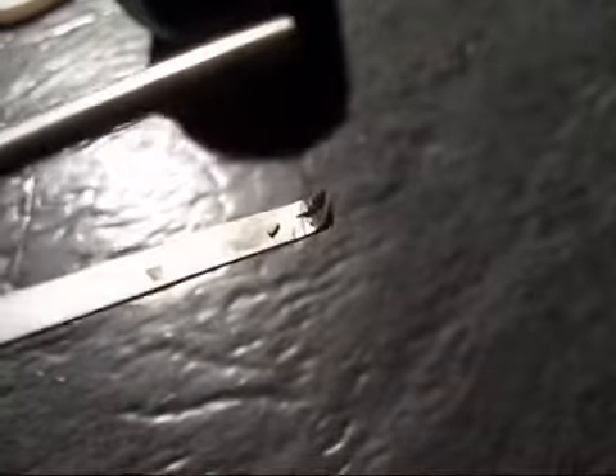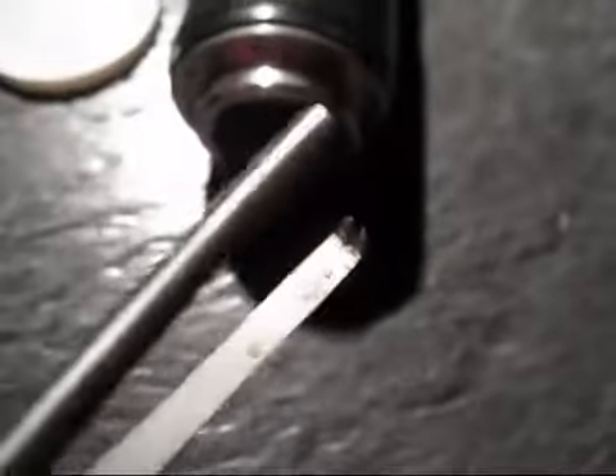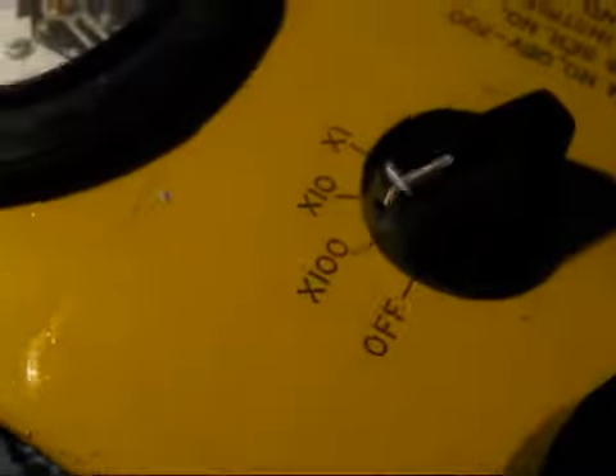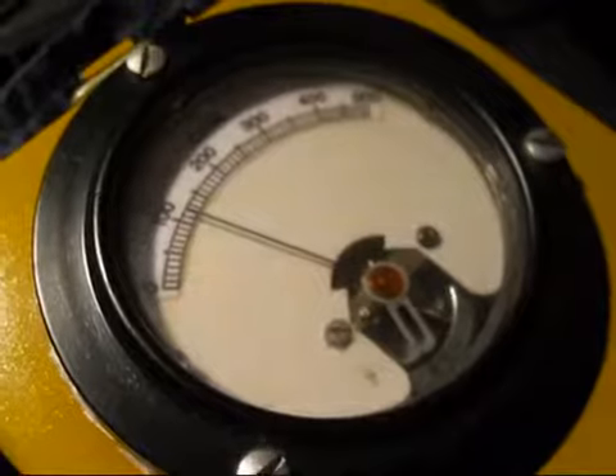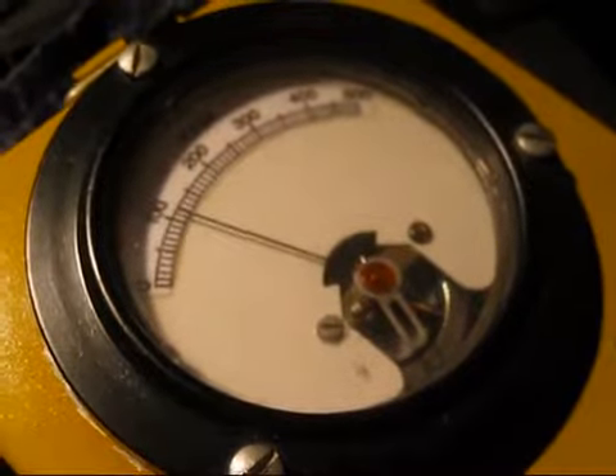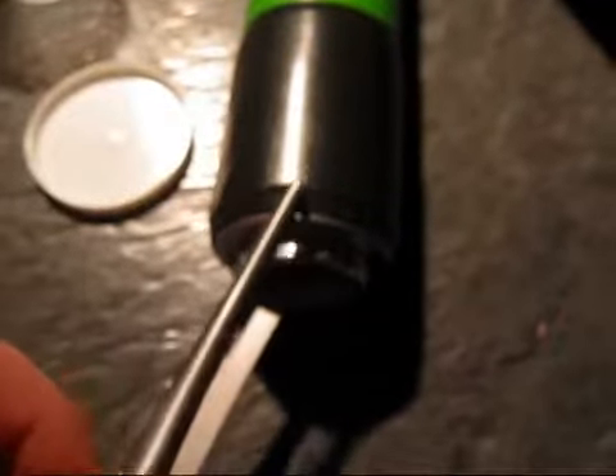Now here's an incredibly tiny amount of radium. Now you can see the tiny white flake on the top of pliers there, because the scintillation counter has a hole in the front where you can insert small samples that will be surrounded by the scintillation crystal. So let's see what happens if I insert this absolutely tiny flake of radium in there. We're on the times 100 setting. You can see we're getting about 10,000 counts per minute from this tiny little piece of radium paint.